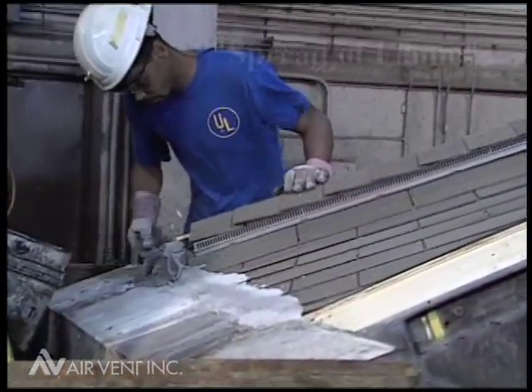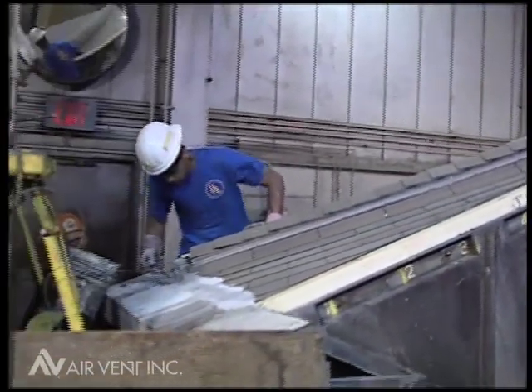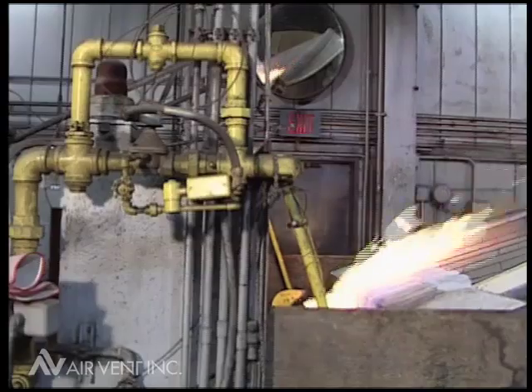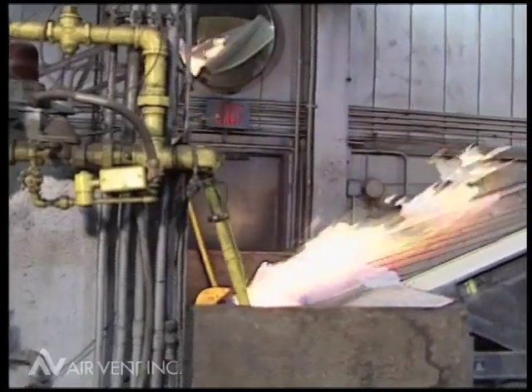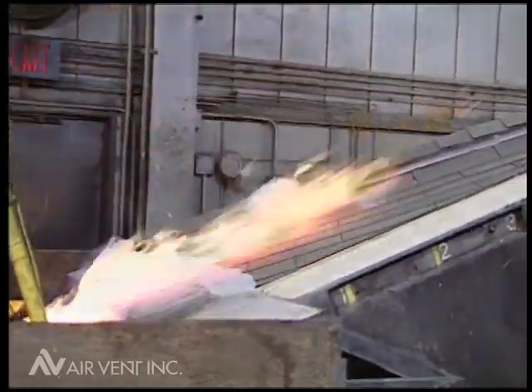In the spread of flame test, Shingle Vent 2-9A was installed on a mock roof deck and was subjected to a 1,400 degree Fahrenheit flame from a gas burner and a 12-mile-per-hour wind for 10 minutes.